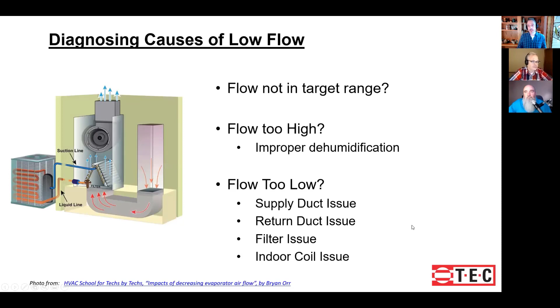Yeah. Okay. So the app is laid out like this. The first thing that you need to do is decide which analysis you want to do. There's really three main analyses that you can pick. The first one is the static pressure and system airflow together. And that, as Bill said before, that's really the best, the most valuable way. If you want to get the most information, that's the way to go. The other two are more for doing a quick check. If you just want to do a system airflow check, say like you said, you've just completed an install and you just want to make sure you're right at the target airflow. Say you designed a system for 400 CFM per ton. You want to make sure, okay, I'm at 415, I'm fine. The third one is also just an airflow, but it specifically follows the ACCA 310 standard to do a grading. It'll give you grade 1, 2, or 3, depending on the airflow and the range that the airflow is in. And so you pick one of those three.